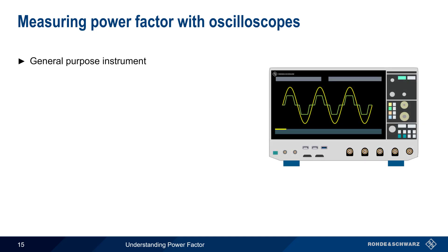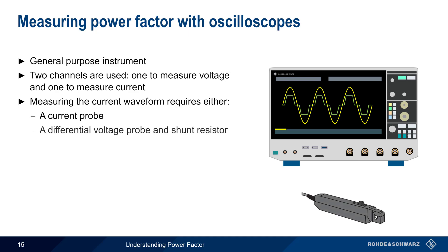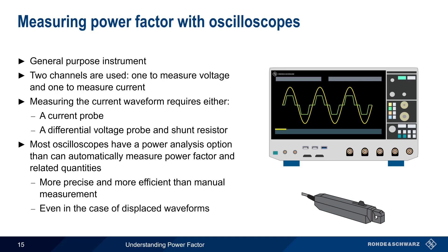Oscilloscopes are more general-purpose instruments that can also be used to measure power factor and the effectiveness of power factor correction. Two channels are needed in this case — one to measure the voltage waveform and one to measure the current waveform. Note that in order to measure current with an oscilloscope, either a current probe or a differential voltage probe and shunt resistor must be used. Many oscilloscopes have a power analysis option that will automatically measure power factor and related quantities. Using a power analysis application is significantly more precise and efficient compared to manual measurement, even in the case of a simple waveform displacement.